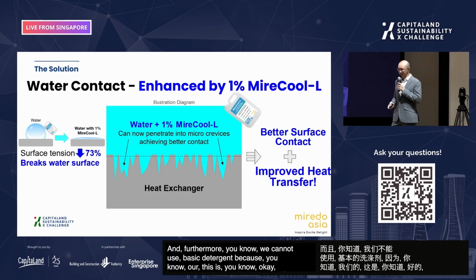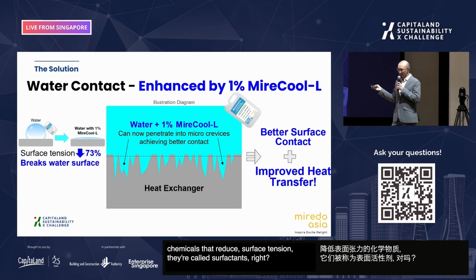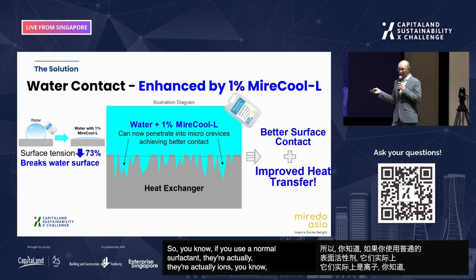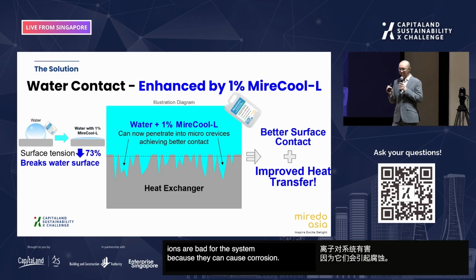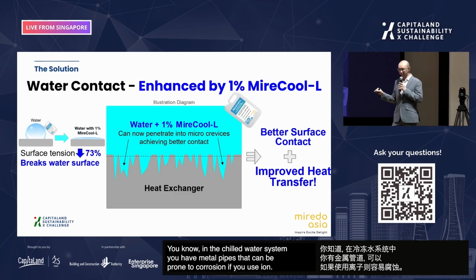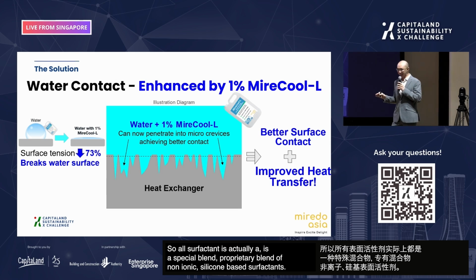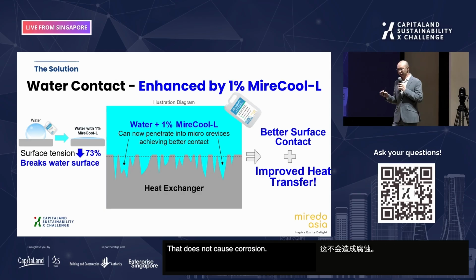And furthermore, we cannot use basic detergents, because chemicals that reduce surface tension—called surfactants—are normally ions. Ions are bad for the system because they can cause corrosion. In a chilled water system you have metal pipes that can be prone to corrosion if you use ion-based surfactants. So our surfactant is actually a special, proprietary blend of non-ionic, silicon-based surfactants that does not cause corrosion.